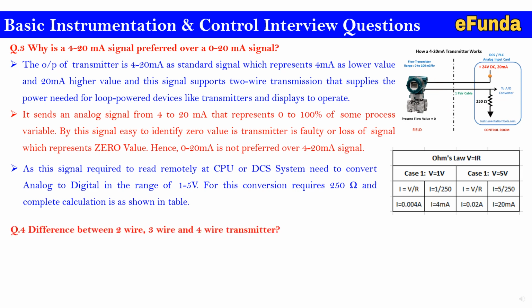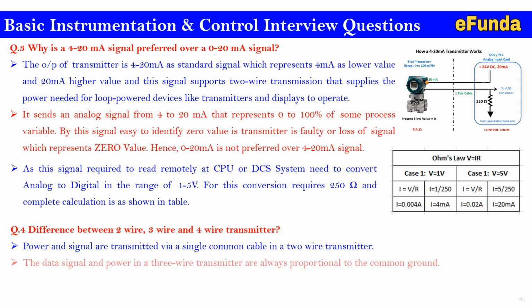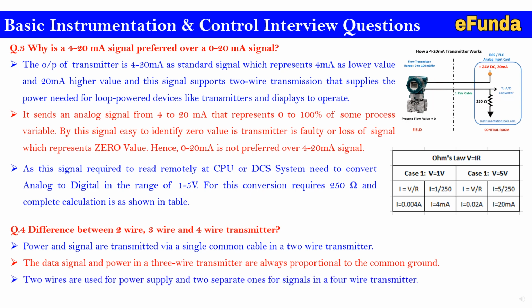Fourth question: difference between 2-wire, 3-wire and 4-wire transmitters. First, power and signal are transmitted via a single common cable in a 2-wire transmitter. Second, the data signal and power in a 3-wire transmitter are always proportional to the common ground. Third, in a 4-wire transmitter combination, 2 wires are used for power supply and 2 separate ones for the signal.